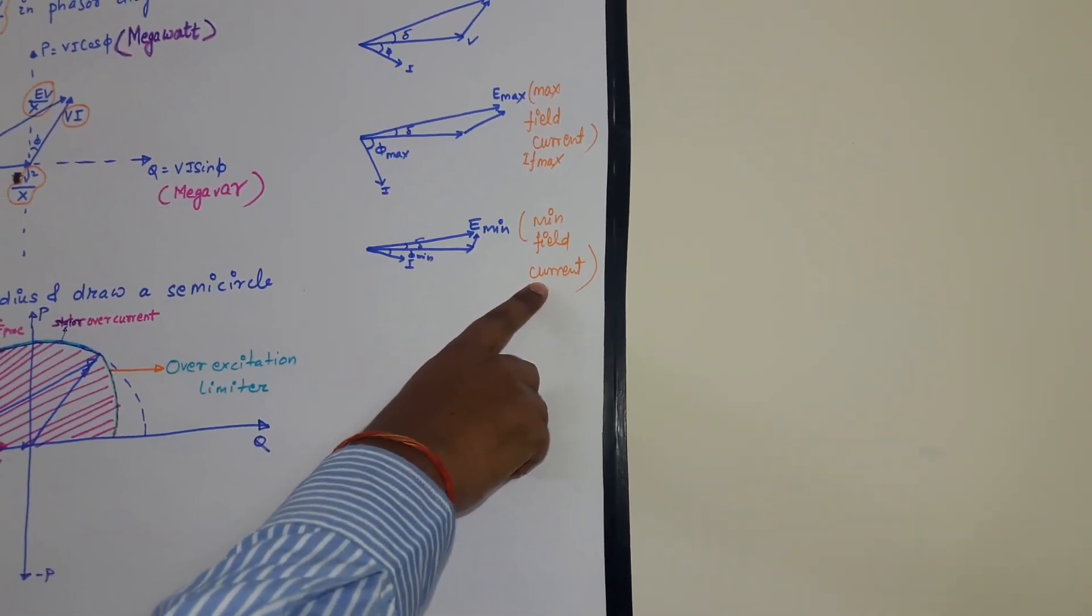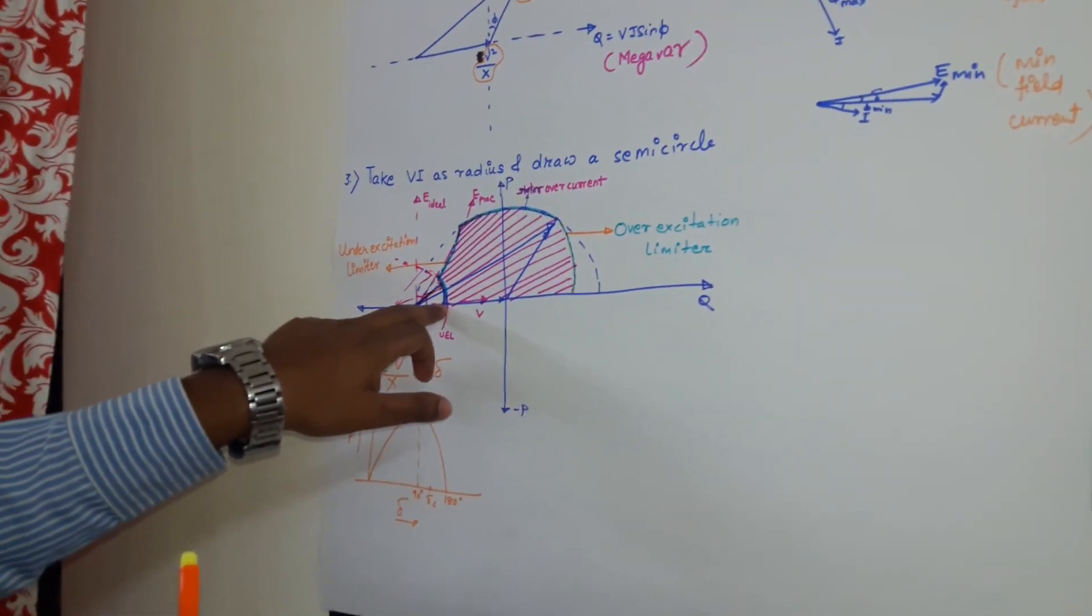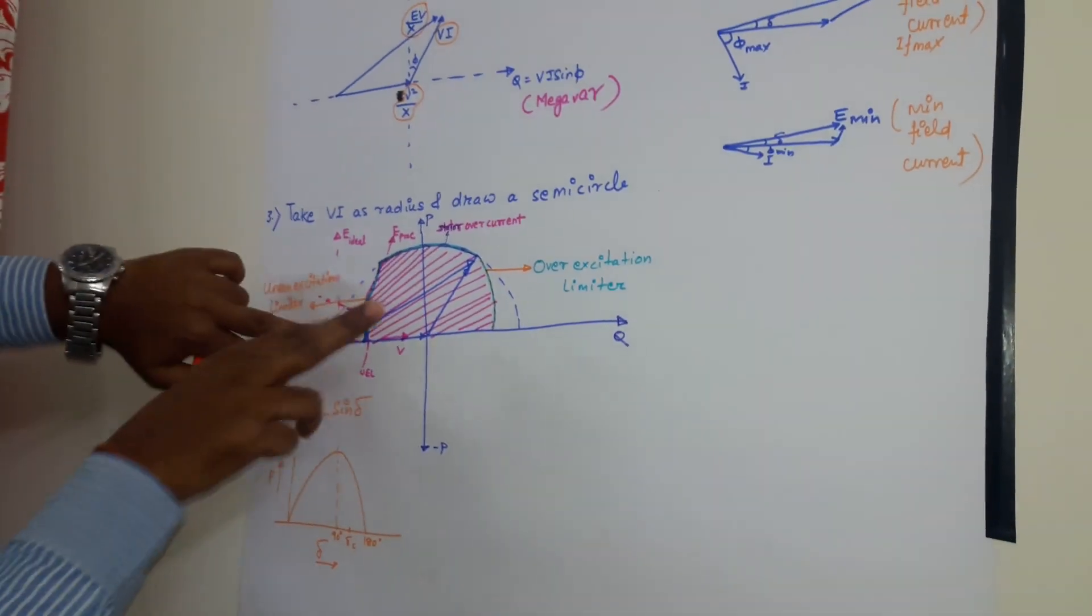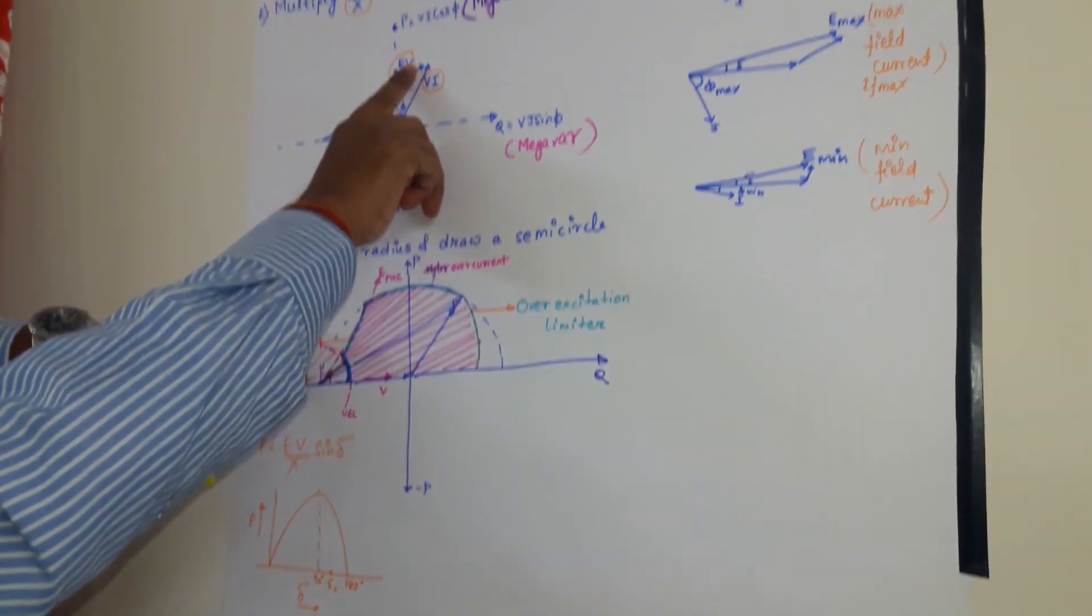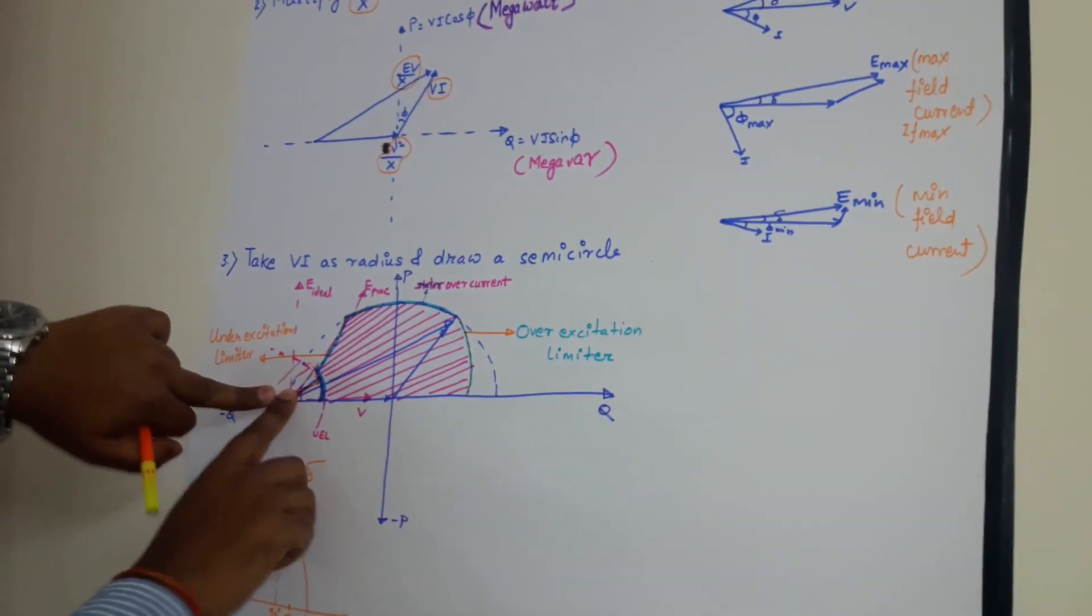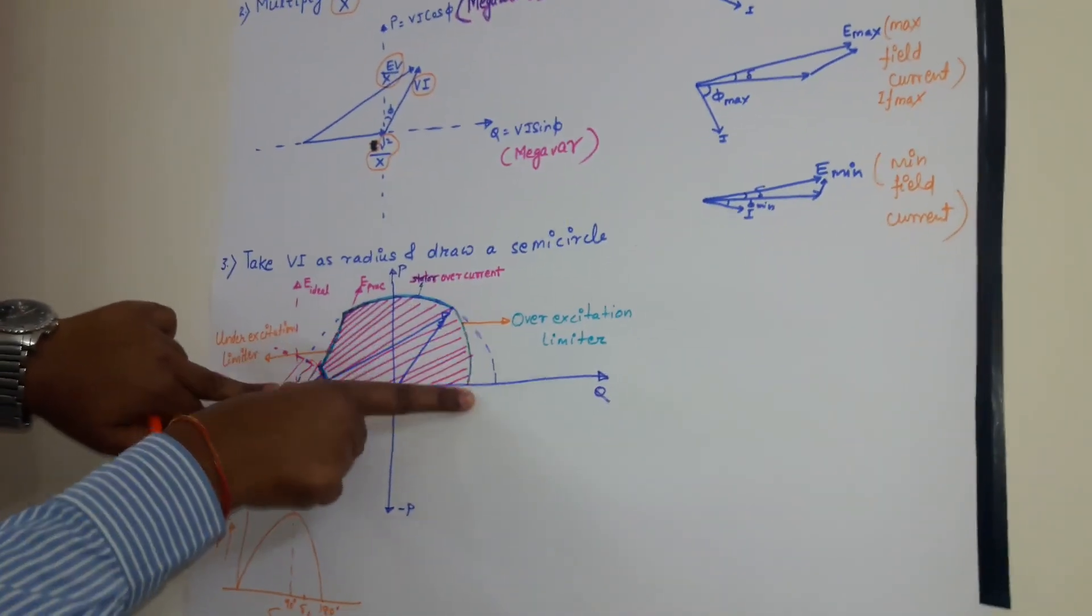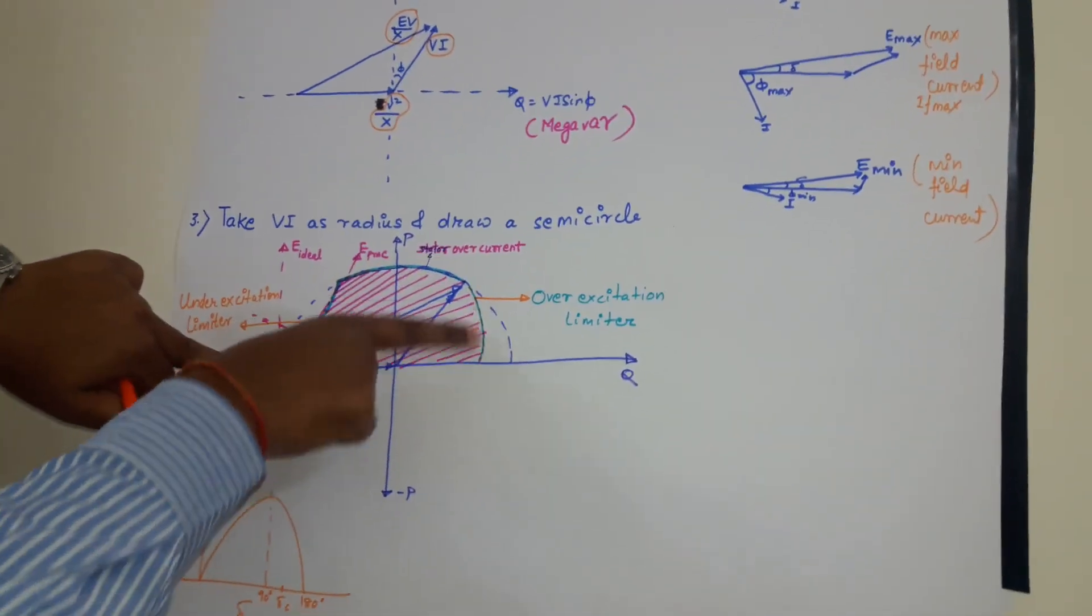At minimum field current, what is happening? We are absorbing reactive power. So at that time also, there are certain regions of generator where overheating may occur.